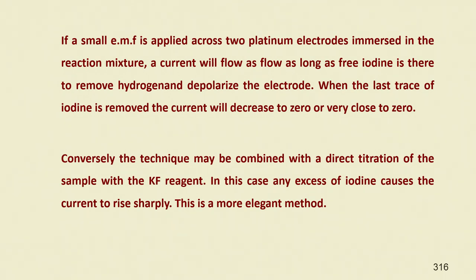When iodine is totally consumed, the current is zero or very close to zero. Conversely, the technique may be combined with direct titration of the sample with Karl Fischer reagent — any excess of iodine causes the current to rise sharply. Initially there is a reducing current; it slowly becomes zero, and then any additional excess reagent from the burette causes the current to start rising again because of excess I₃⁻ ions.